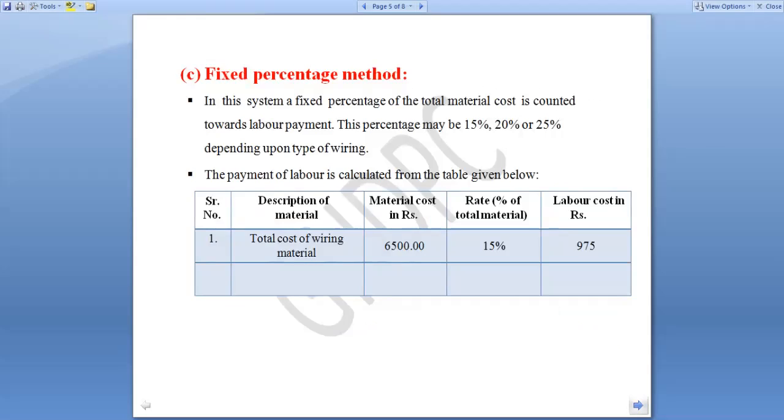The third method is the fixed percentage method. In this system, it is the easiest of them all, I think. A fixed percent or a fraction of the total raw material cost is counted. And it is decided whether you have to pay 15%, 20 or 25, depending on the type of wiring you are using. And going through the table, the description of the material, that is, the total cost of the wiring material and the raw material cost, comes to be 6,500.